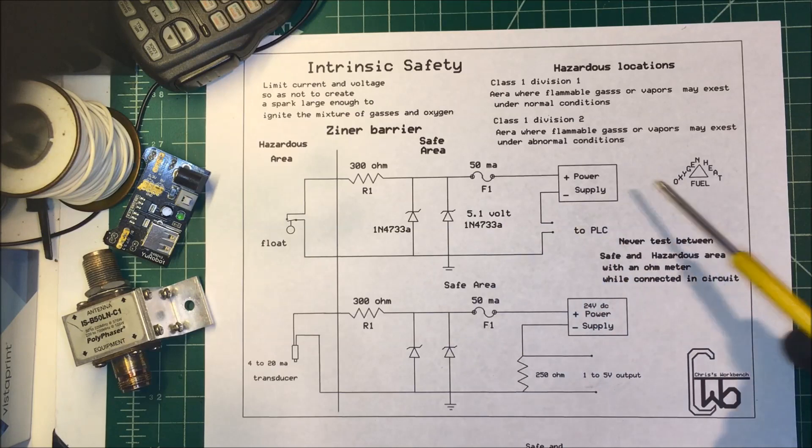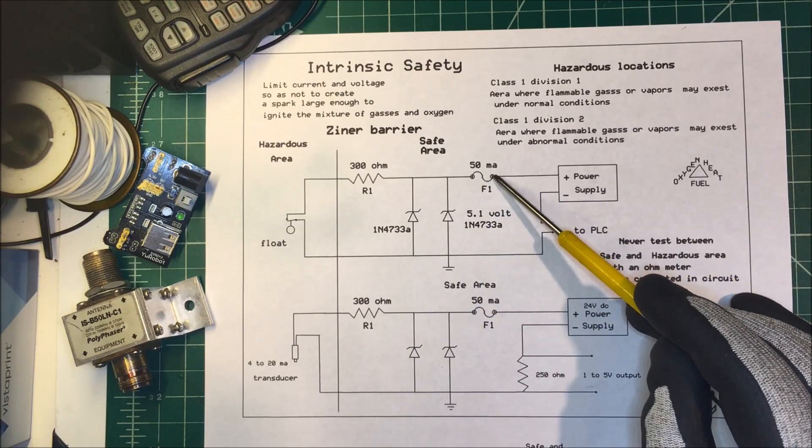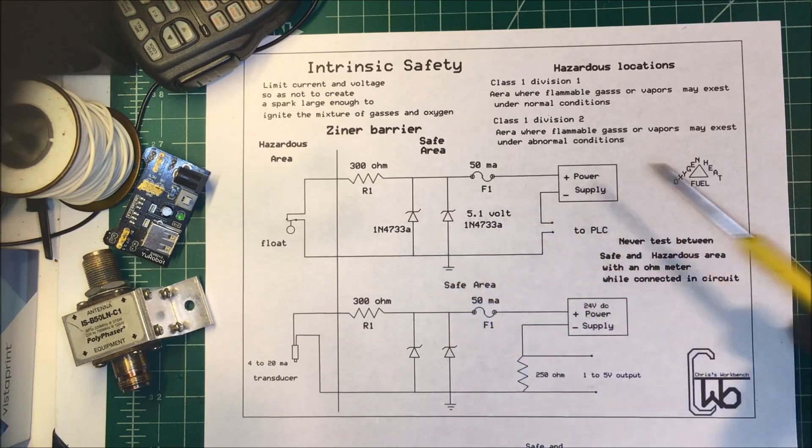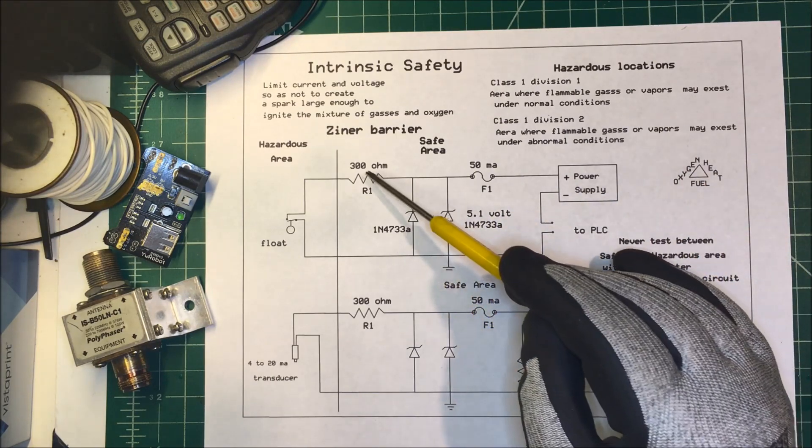So we use this Zener barrier. It has just three components: a fuse, usually about 50 milliamp, then a couple of Zener diodes, maybe two or three just for redundancy, and then some kind of resistor to limit the current into that area.